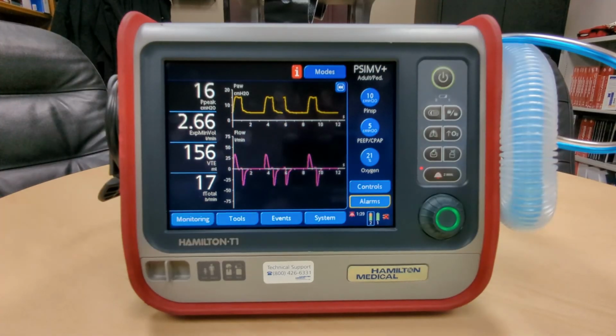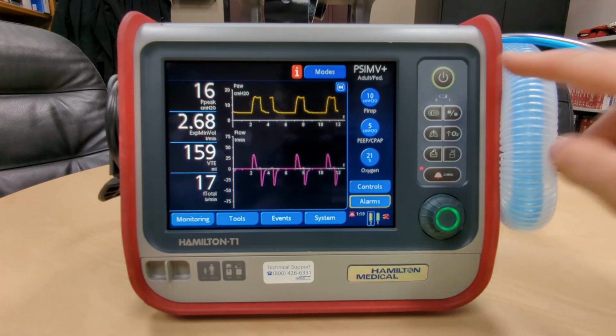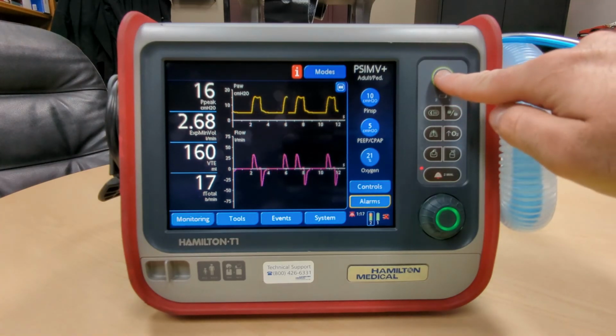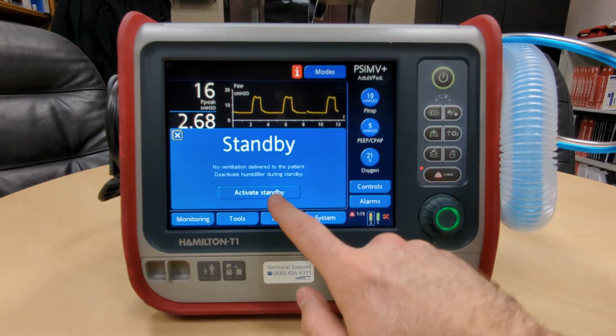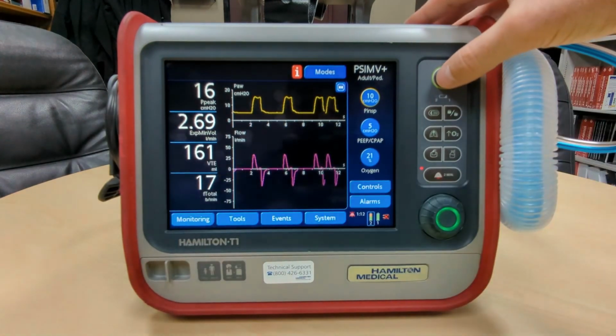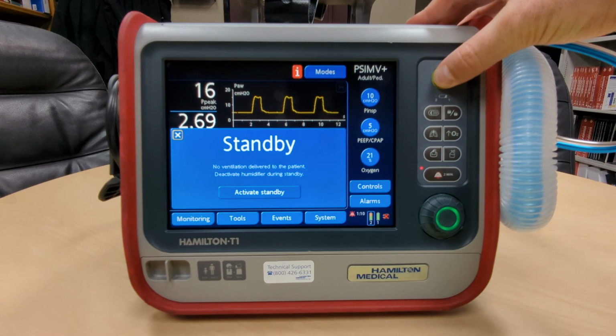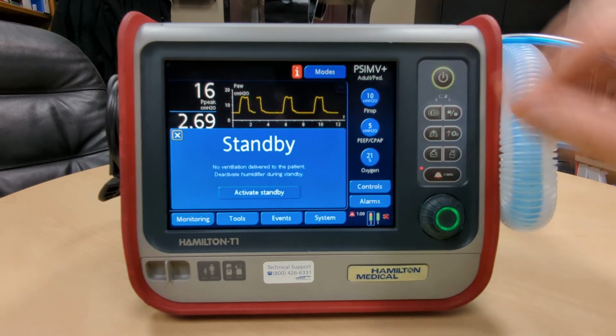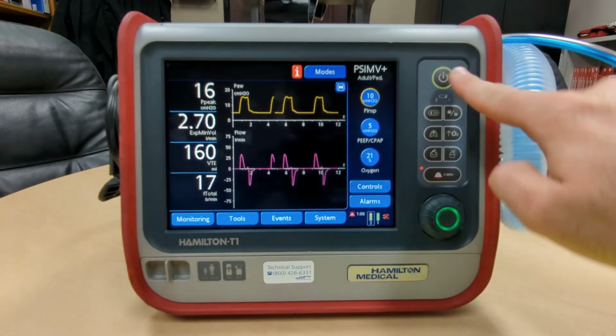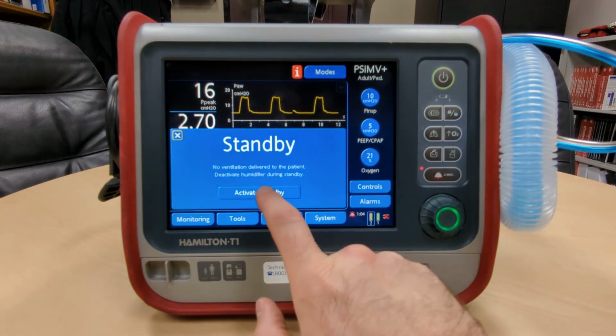Another caveat. When you've reached your destination and you're getting ready to transfer the patient from your ventilator to the other one, and you're ready to turn this ventilator off, you must first press the power button, tap, and then select standby. If you do not, and try to hold the power button down, it will not turn off. So again, tap the power button, and then hit activate standby.